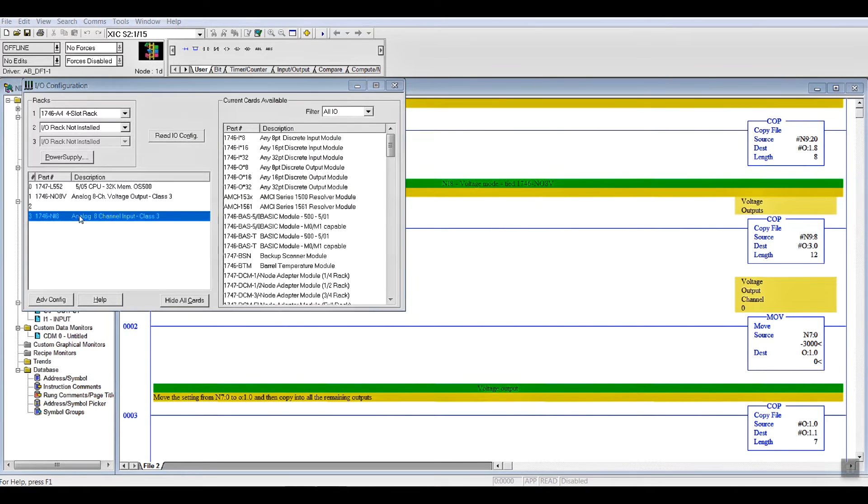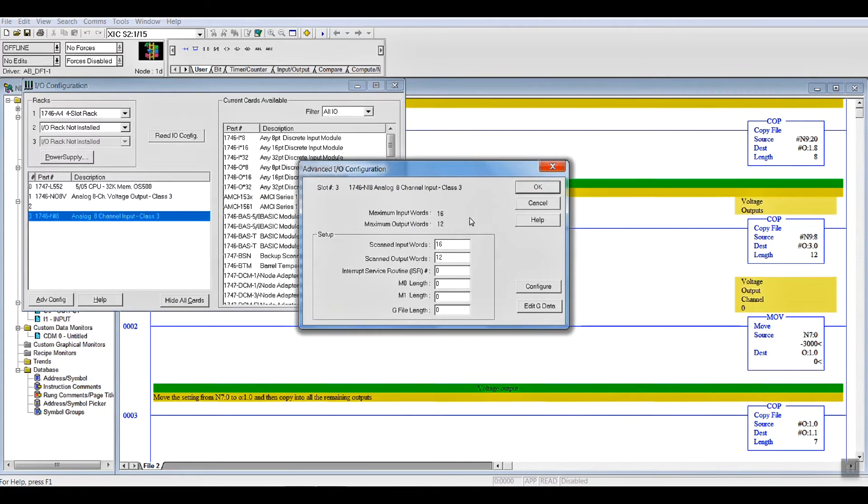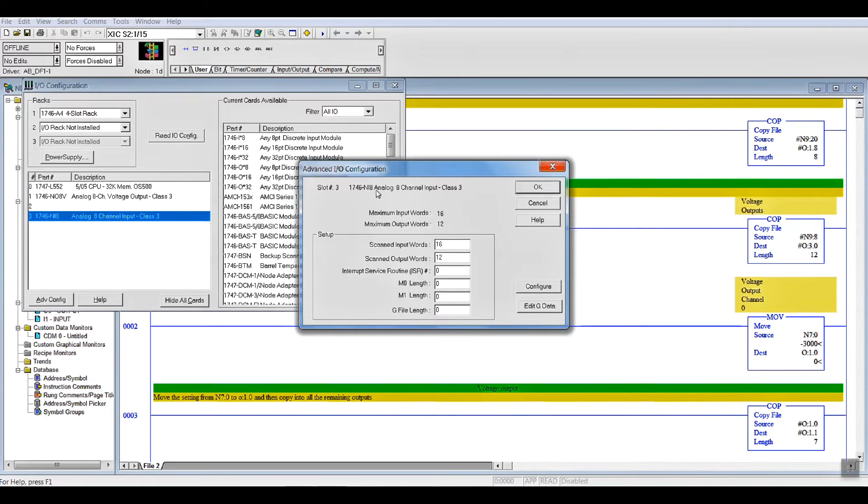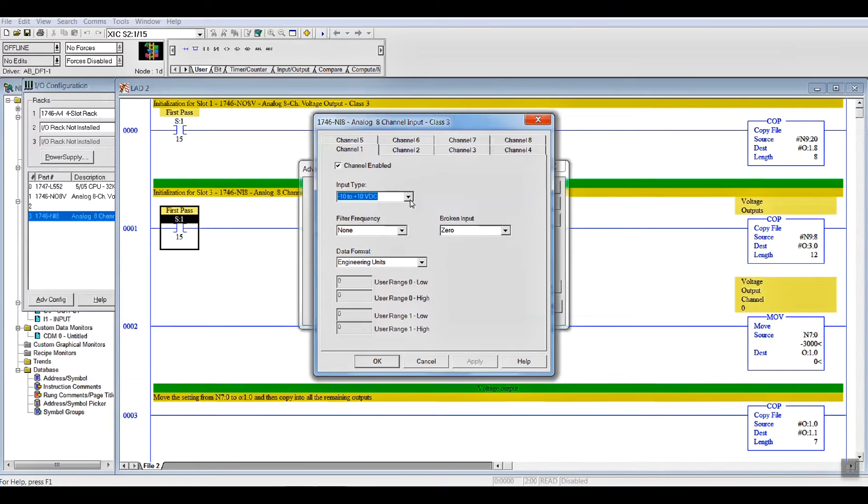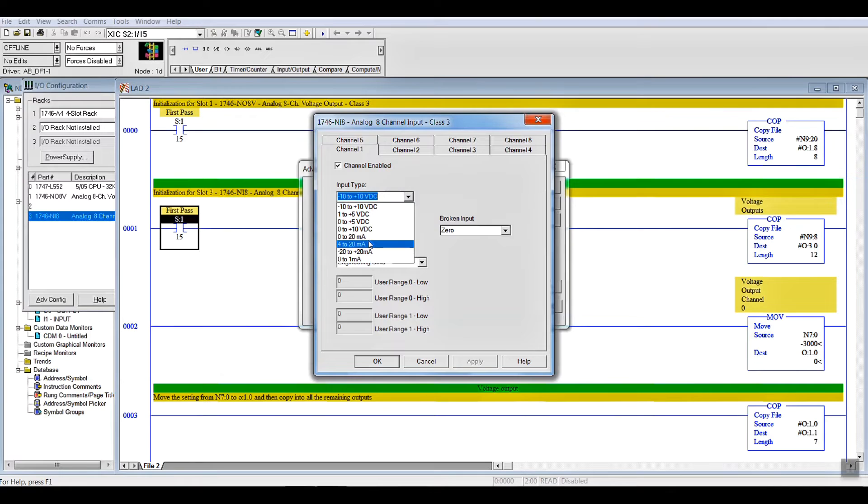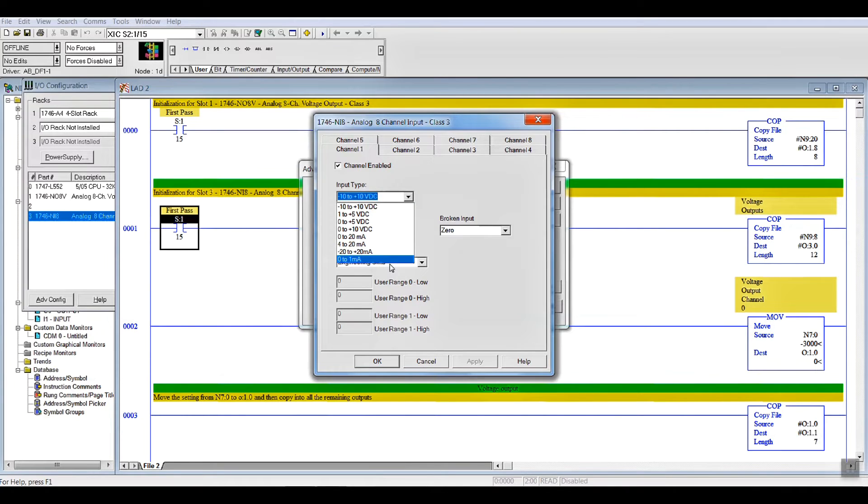Our input card does the same thing. It's the same sort of screen. It's just that it says NI8 Input. Go to Configure. You have to enable the channels you want. And, on the input type, you have voltage and milliamps. And, remember, you have to set the slide switch to match what you're putting into the card.